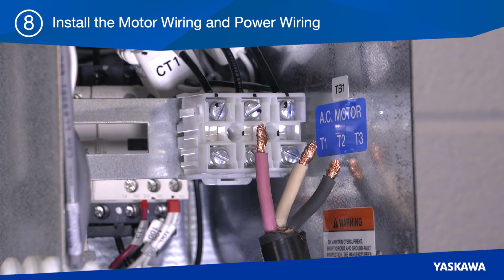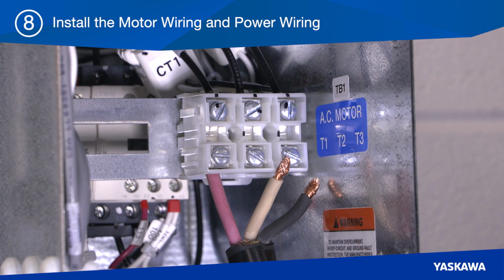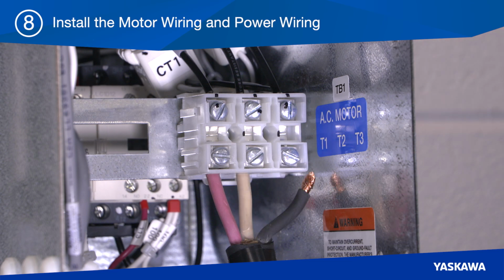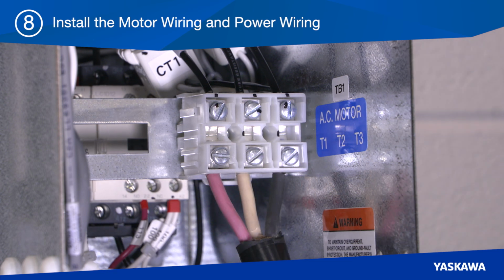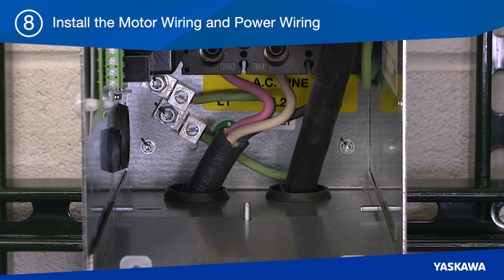Connect the motor wires to the output terminals T1, T2, and T3. And don't forget to connect the motor ground to the bypass cabinet's ground terminal.